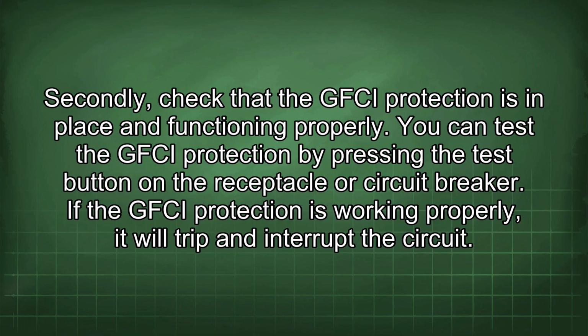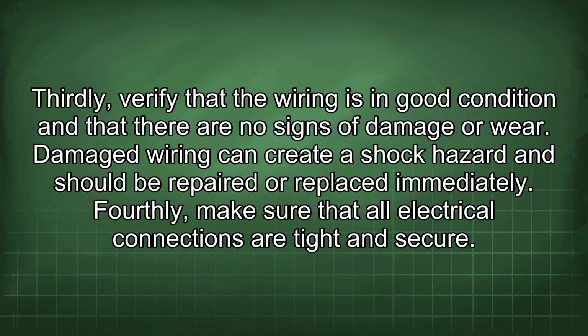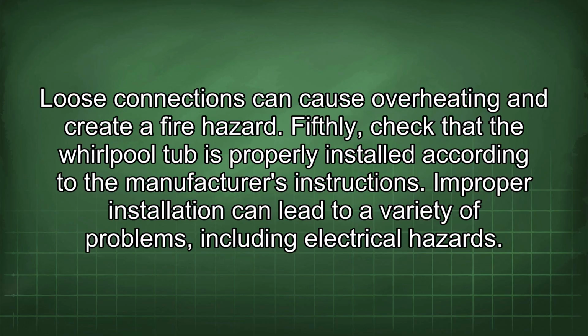You can test the GFCI protection by pressing the test button on the receptacle or circuit breaker. If the GFCI protection is working properly, it will trip and interrupt the circuit. Thirdly, verify that the wiring is in good condition and that there are no signs of damage or wear. Damaged wiring can create a shock hazard and should be repaired or replaced immediately. Fourthly, make sure that all electrical connections are tight and secure. Loose connections can cause overheating and create a fire hazard. Fifthly, check that the Whirlpool tub is properly installed according to the manufacturer's instructions. Improper installation can lead to a variety of problems, including electrical hazards.